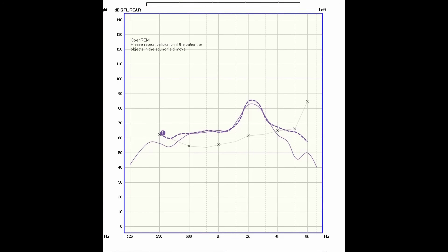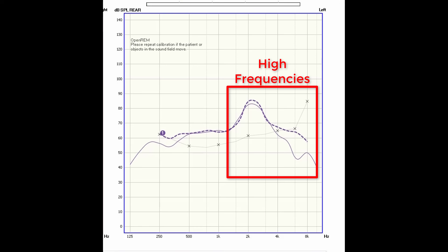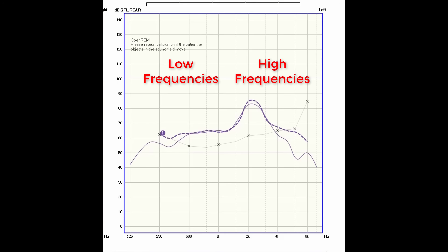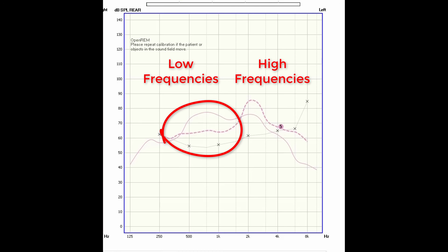The hash mark line is the prescription for your hearing loss, and the solid line is the amplification from your hearing aid. Ideally, you would want the solid line to overlap with the hash mark line as closely as possible. On the right-hand side you have the high frequency measures, and on the left-hand side you have the low frequency measures. There is a pretty good match of the purple hash mark prescription line with the solid amplification line in a good example. But in a case of bad programming — with the pink hash mark target and the solid pink lines — we are over-amplifying the low frequency sounds and under-amplifying the high frequency sounds. This is a perfect recipe for upward spread of masking. If you want to learn more about real ear measurement, I will link my video on that in the description.